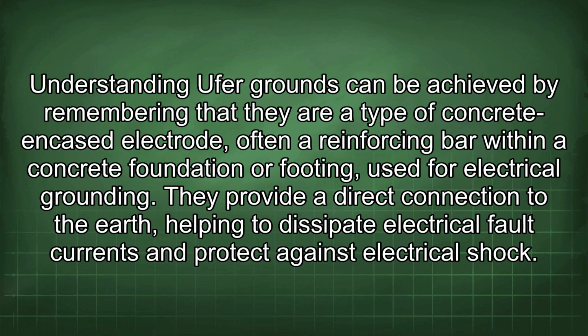Understanding Ufer grounds can be achieved by remembering that they are a type of concrete-encased electrode, often a reinforcing bar within a concrete foundation or footing used for electrical grounding. They provide a direct connection to the earth, helping to dissipate electrical fault currents and protect against electrical shock.